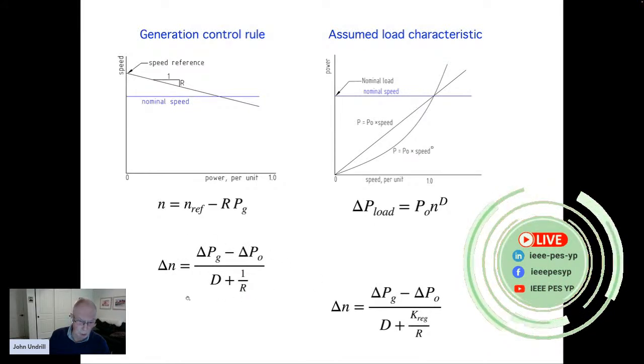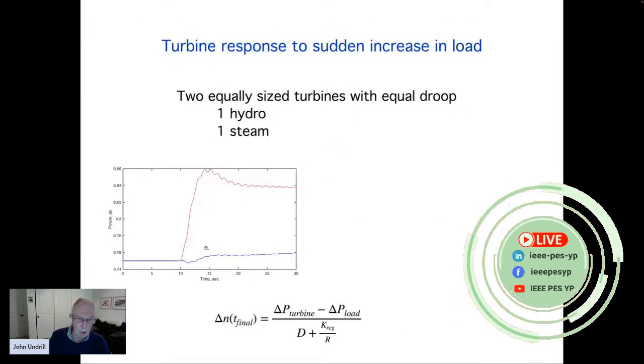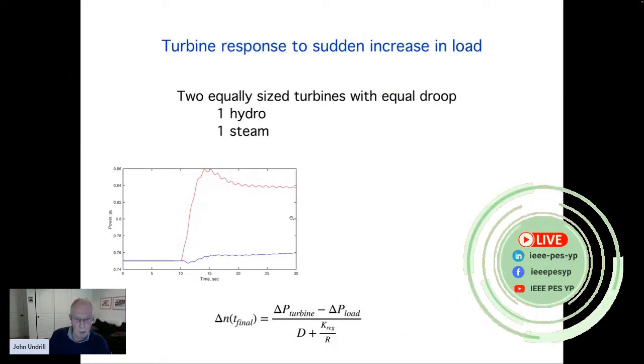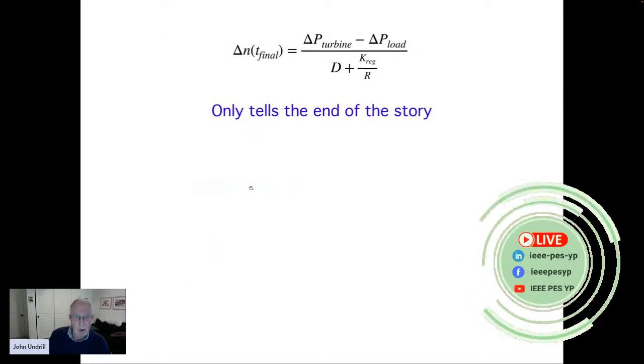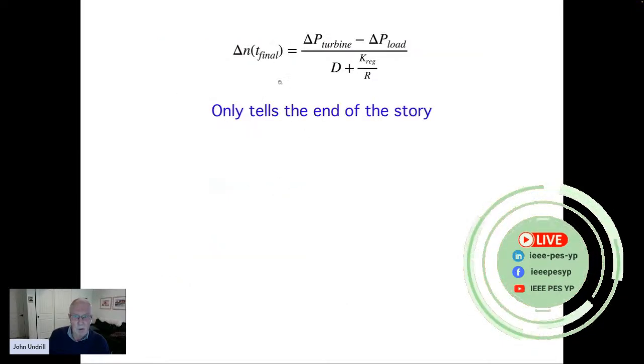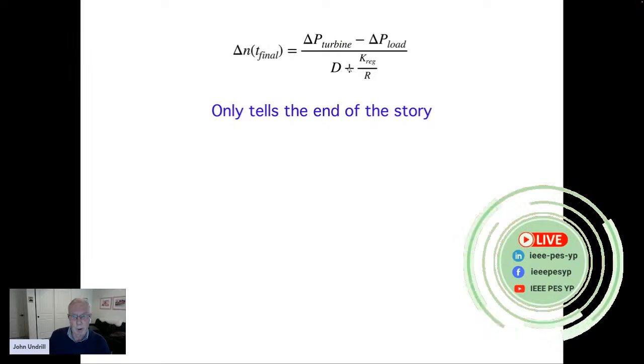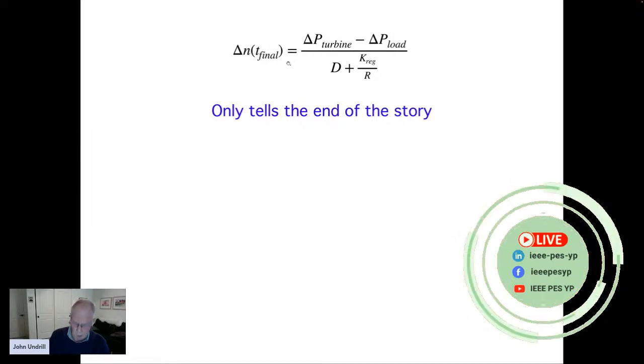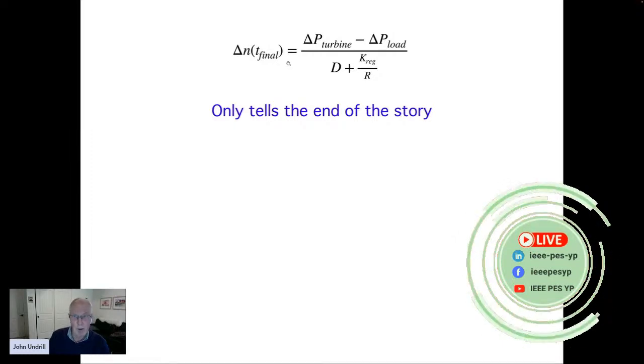Let's assume it should have been this one. Our droop equation didn't work. The droop equation said that the two units would go to an equal output, and they didn't. Why? Well, this droop equation only tells the end of the story. It tells where we expect the power to go, where we expect the speed of the machine to go, but it doesn't tell us how it goes. It only tells us where it's aiming to go.